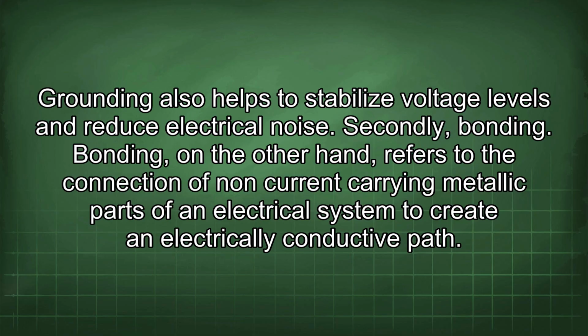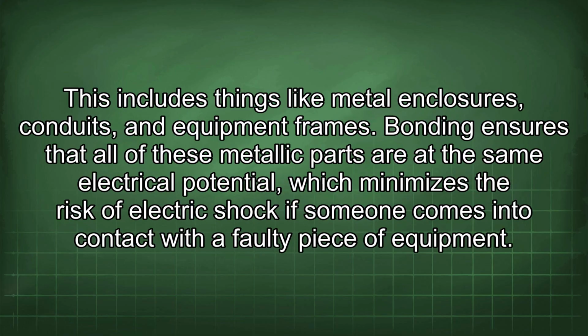Secondly, bonding. Bonding, on the other hand, refers to the connection of non-current carrying metallic parts of an electrical system to create an electrically conductive path. This includes things like metal enclosures, conduits, and equipment frames. Bonding ensures that all of these metallic parts are at the same electrical potential, which minimizes the risk of electric shock if someone comes into contact with a faulty piece of equipment.